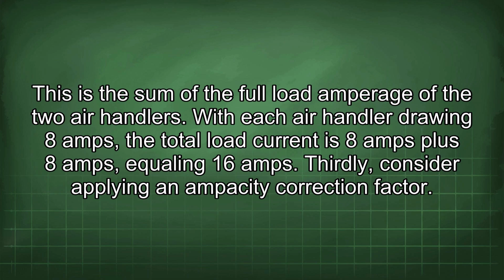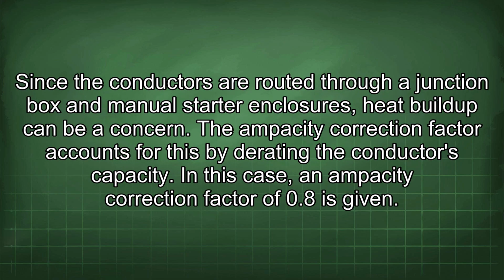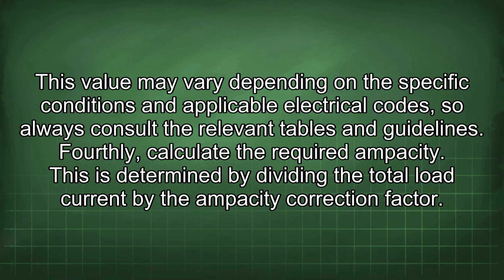Thirdly, consider applying an ampacity correction factor. Since the conductors are routed through a junction box and manual starter enclosures, heat buildup can be a concern. The ampacity correction factor accounts for this by derating the conductor's capacity. In this case, an ampacity correction factor of 0.8 is given. This value may vary depending on the specific conditions and applicable electrical codes, so always consult the relevant tables and guidelines.